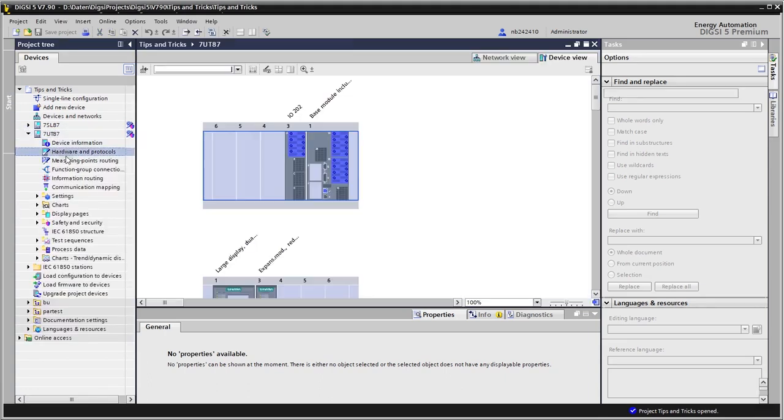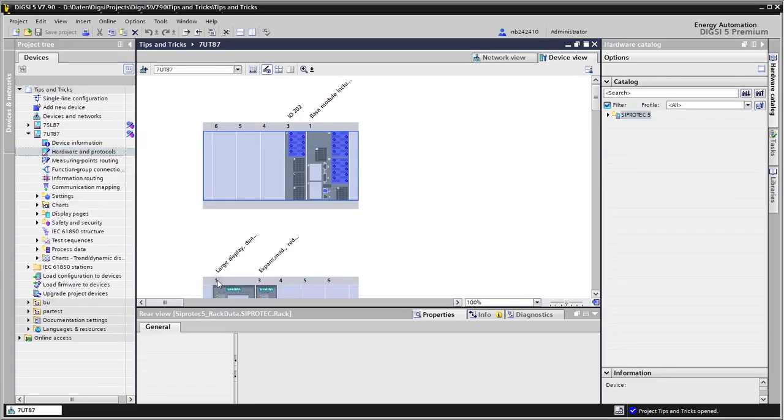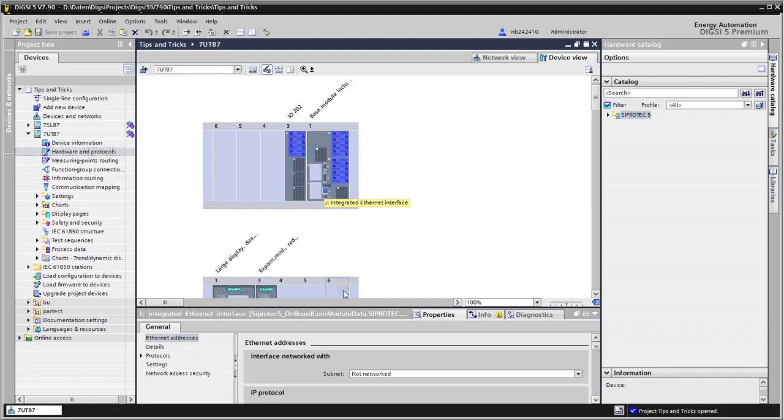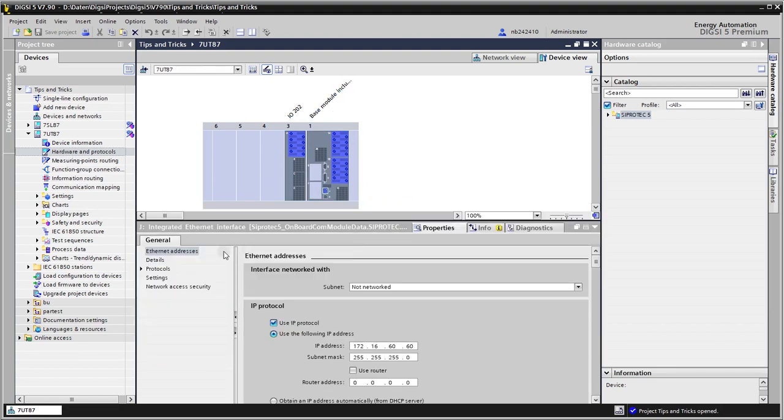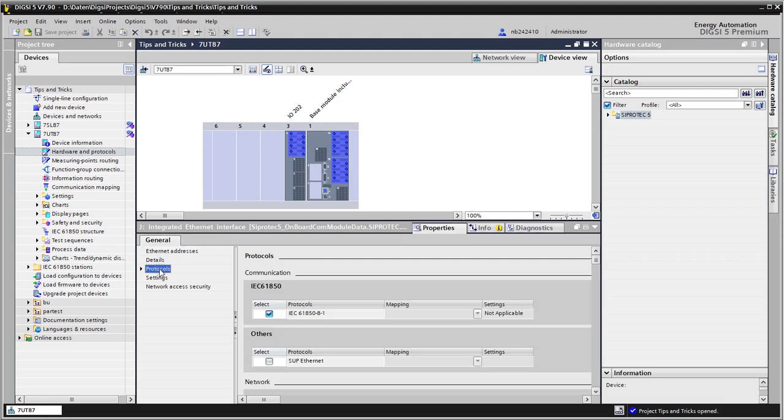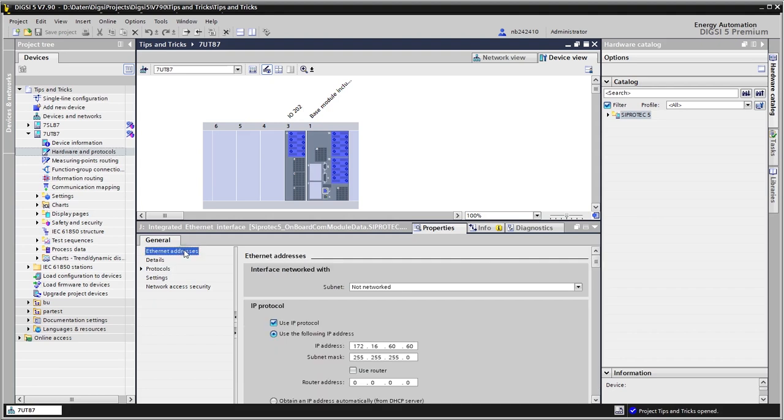We go to hardware protocols and I use the port J, so I mark the port J and here under protocols we see IEC 61850 is already selected. And it makes sense also to adjust here the IP address right from the beginning if I have another range of addresses than the normal one. I leave it here with the standard IP addresses.